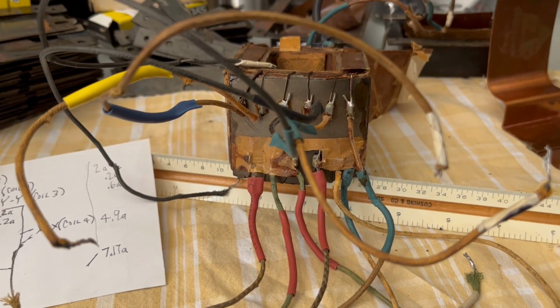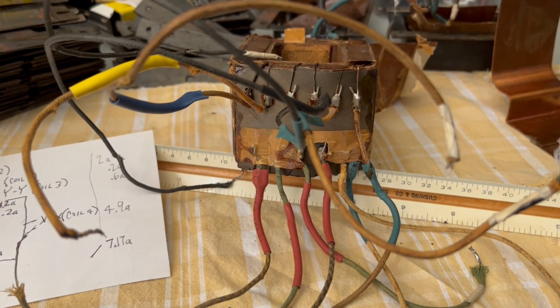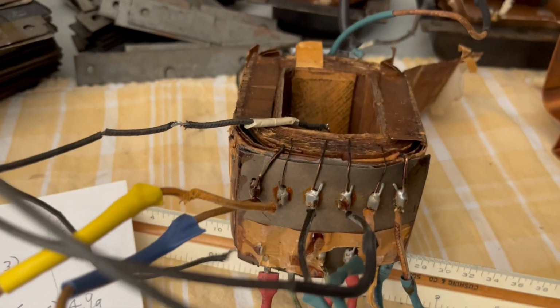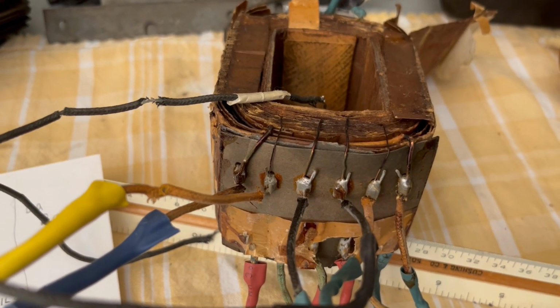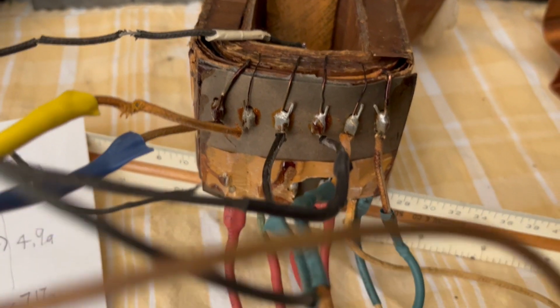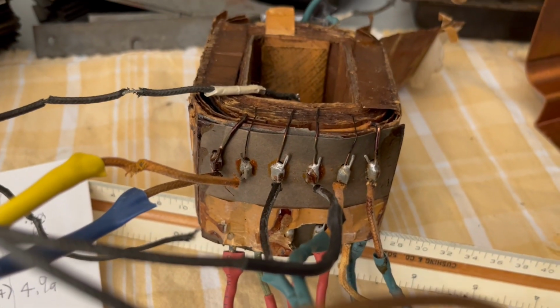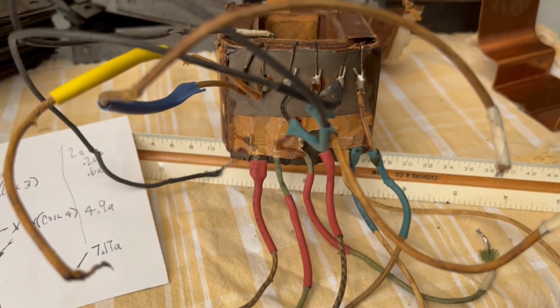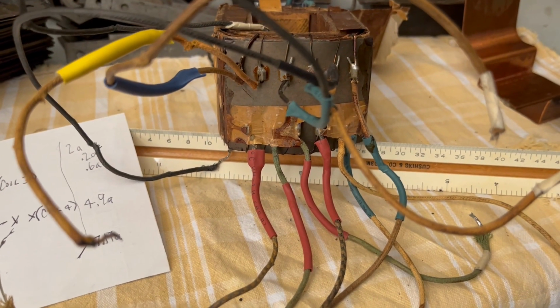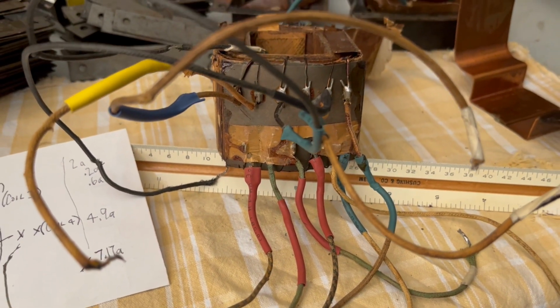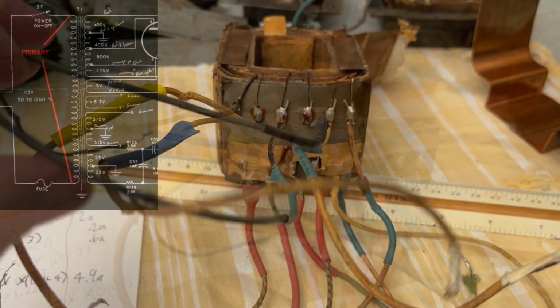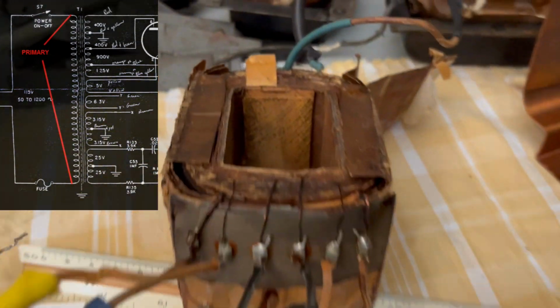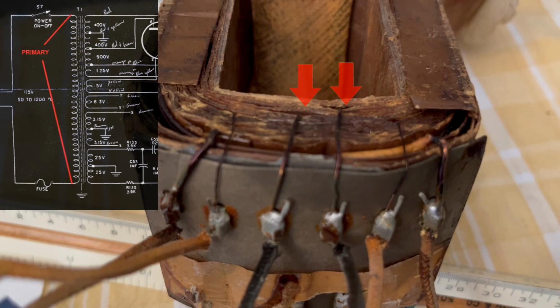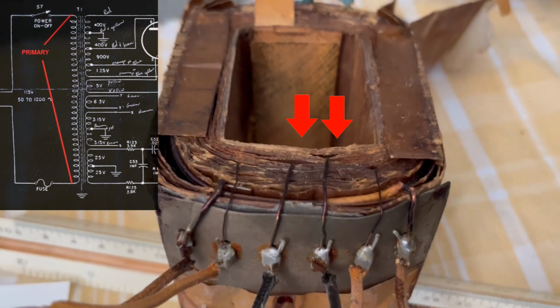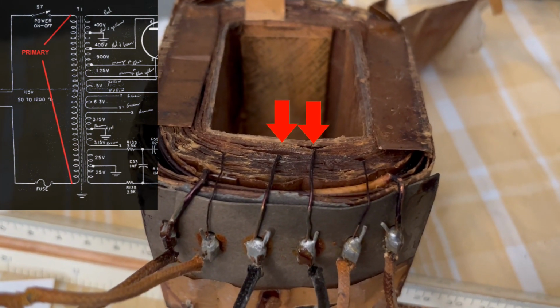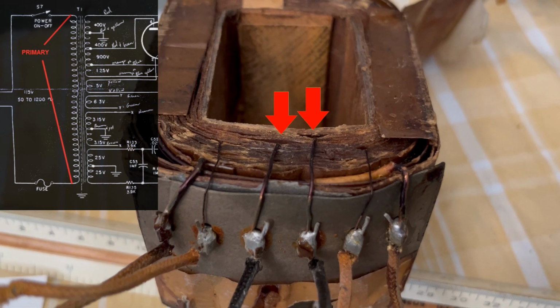What you can see is there's points of termination that come out of the coil. You can see the wires coming out of the coil there. They tie down, and then the leads going out to the world. The layout on this transformer is in the center. You can see these are the primary leads here, the two black ones. They're in the very middle. And if you look where they go under the coil, it's way down to the base of the coil. So the primary looks like it's the innermost part of the coil.